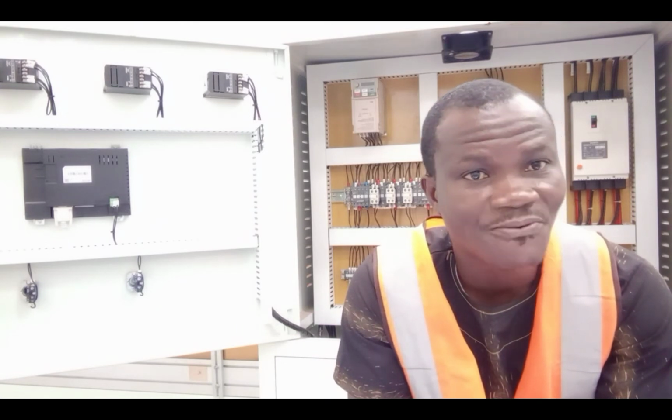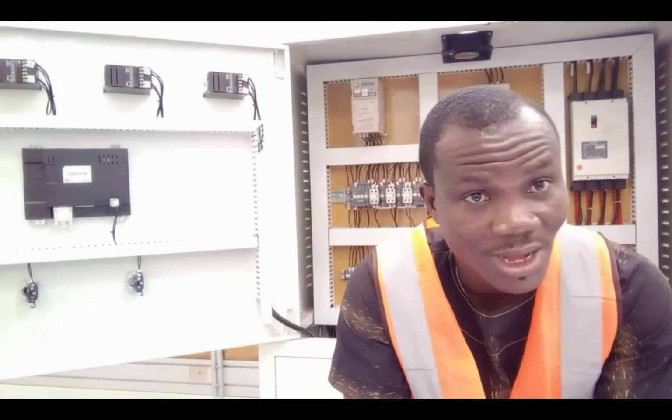All right, so from the standard rating of circuit breakers we have, under 17 amps, we have 16 amps, we have 10 amps, we have 6 amps. So these are the list of circuit breakers that you can select from to protect this particular circuit. The breaker you select for protecting the load shouldn't have a rating that is higher than the current capacity of the cables in the circuit.